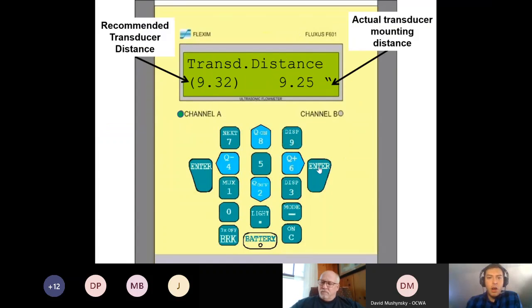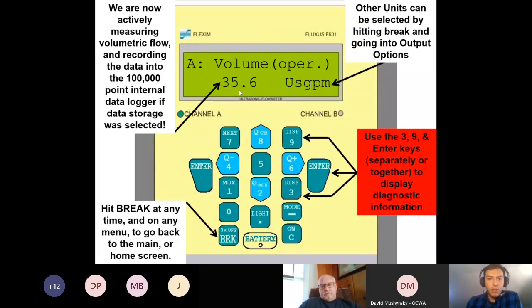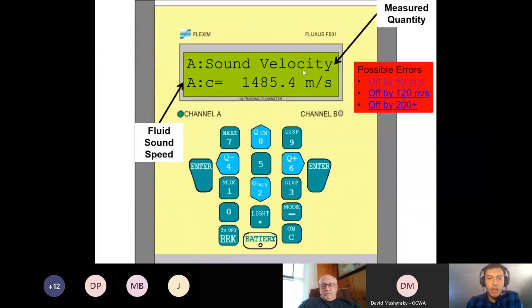Other diagnostics that you want to look for when you're in this gallons per minute menu: if you hit the 3 button, you will see the sound velocity. This should also be in the pipe lookup chart. Again, please let us know if you don't have this, and we can definitely send it over to you. Our ultrasonic beams move through every medium at a different speed at different temperatures. So, for example, 1485 is a little bit warmer than room temperature water. You would just have to look up the temperature that you're at in that sound speed lookup chart. You're allowed to be plus or minus 50 for your sound speed.